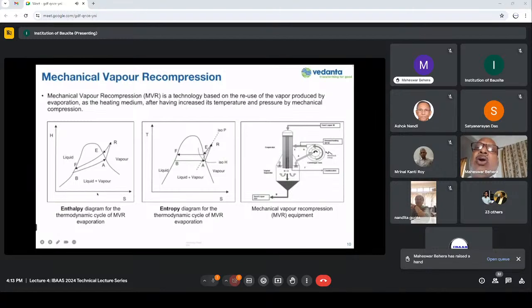Mechanical vapor recompression, or MVR, is a technology based on the reuse of waste vapor as a heating medium after having increased its temperature and pressure by mechanical compression. A typical MVR equipment is a set of compressors, which can be centrifugal or axial, which increase the temperature and pressure of the vapor. In the figure, an MVR setup for falling film evaporation is shown.